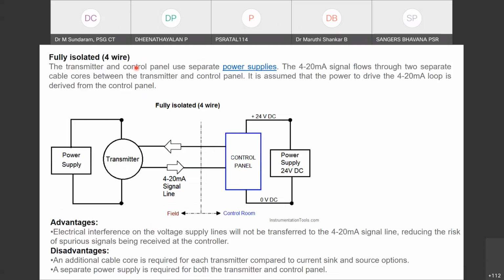So any analog sensor, whether pressure, flow, or temperature, can be 2-wire, 3-wire, or 4-wire. You can't use 4-wire everywhere because it's costly, since you need a separate power supply for the transmitter and a separate one for the controller. It all depends on the application. If it's sensitive, go for 4-wire; otherwise, stop with 2 or 3.